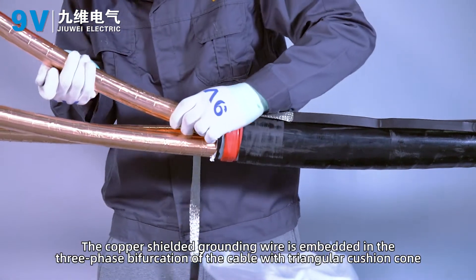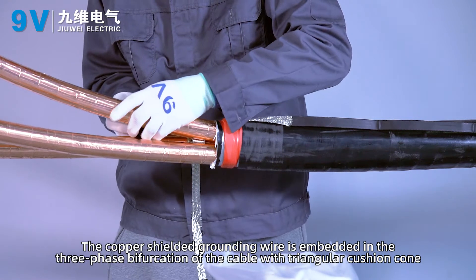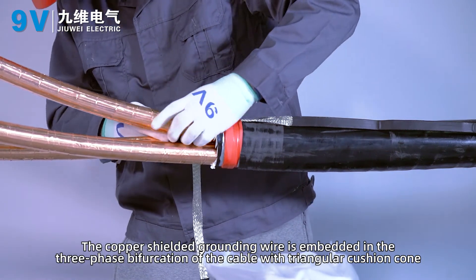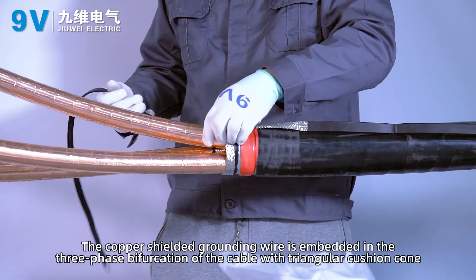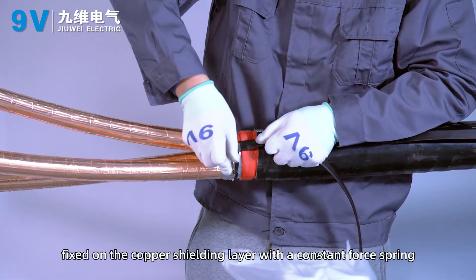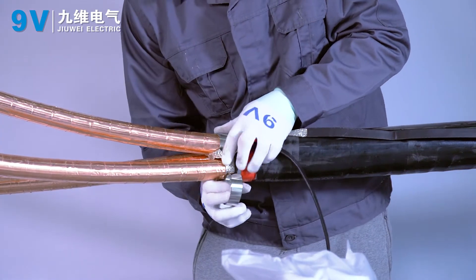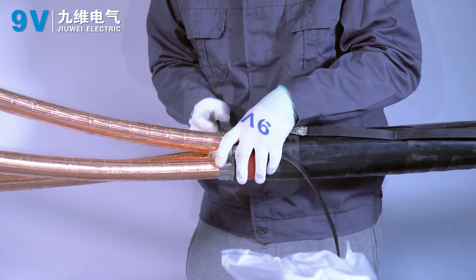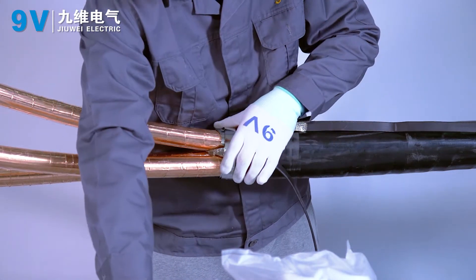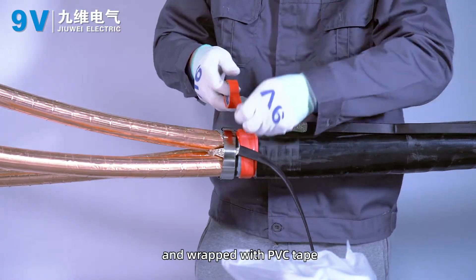Wrap the constant force spring with PVC tape. The copper shielded grounding wire is embedded in the three-phase bifurcation of the cable with a triangular cushion cone, and fixed on the copper shielding layer with a constant force spring. Wrap with PVC tape.